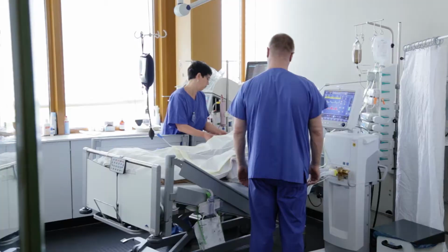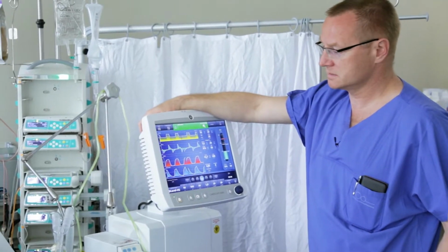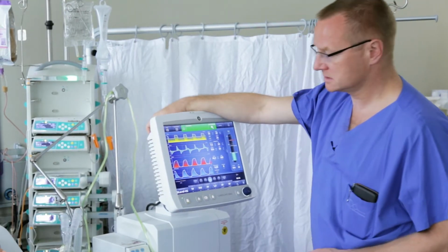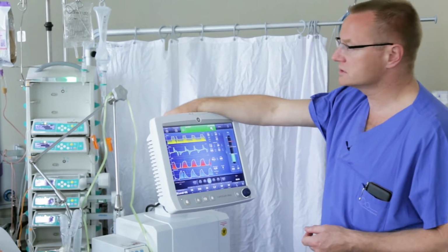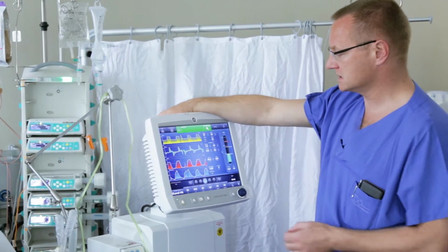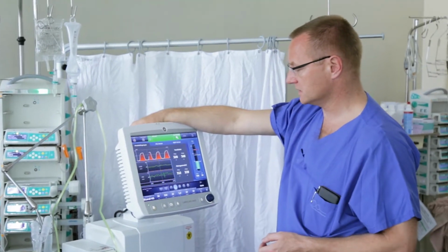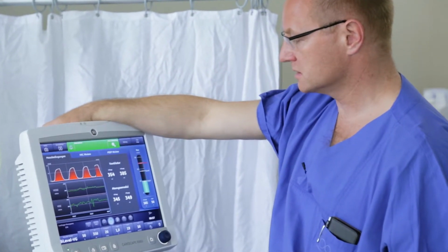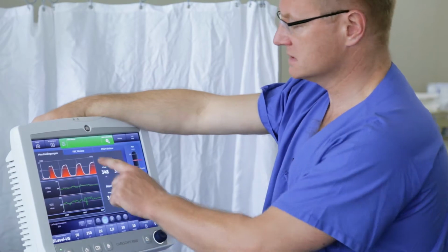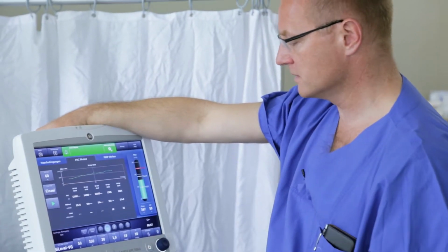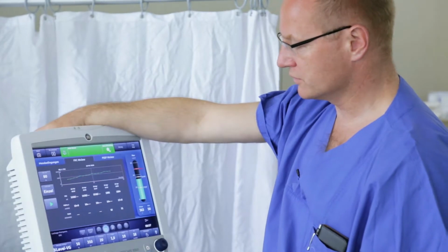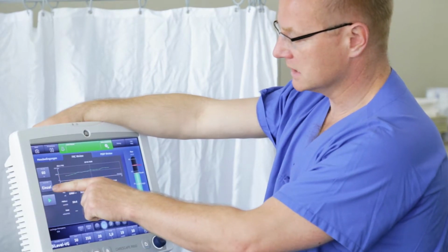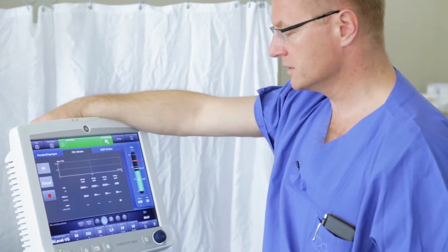So let us begin. Here we have a 76-year-old critically ill patient with renal failure resulting from pneumonia. The patient requires administration of catecholamines and ventilation. The first thing we will do is control the conditions for the measurement of functional residual capacity, FRC. We see that the VCO2 value is relatively stable. We can assume, therefore, that the measurement will be reliable. With the aid of FRC in-view, I will now perform a single measurement, 50% oxygen, 10% change, single measurement. I will press the green button and the measuring will begin.